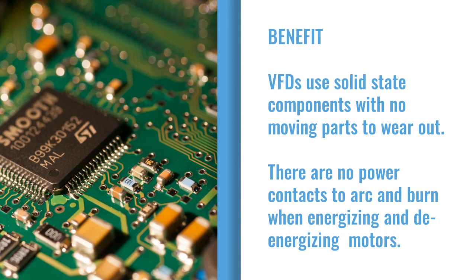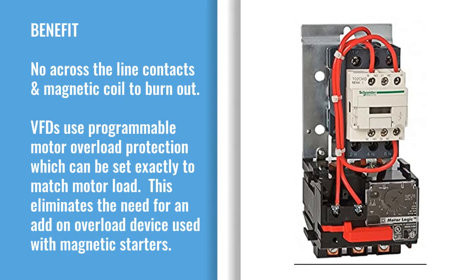VFDs use solid state components with no moving parts to wear out. There are no power contacts to arc and burn when energizing and de-energizing motors, and no across-the-line contacts and magnetic coil to burn out.